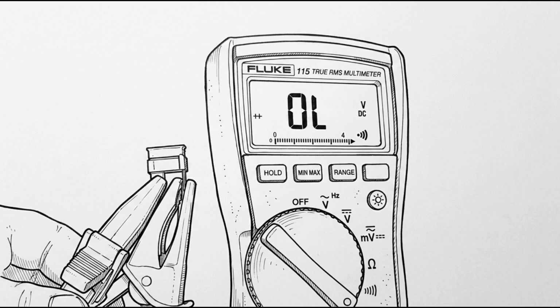Don't let the probes touch each other during this test, as that creates a short circuit showing near 0 volts. If unsure whether your meter is working correctly, touch the probes together separately to confirm a near 0 reading.